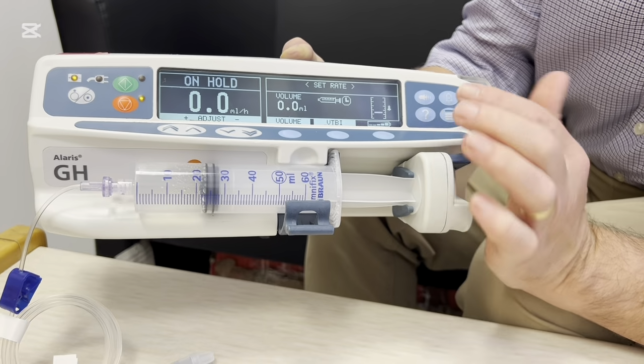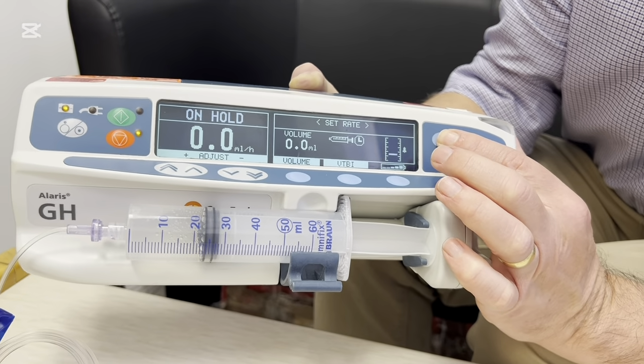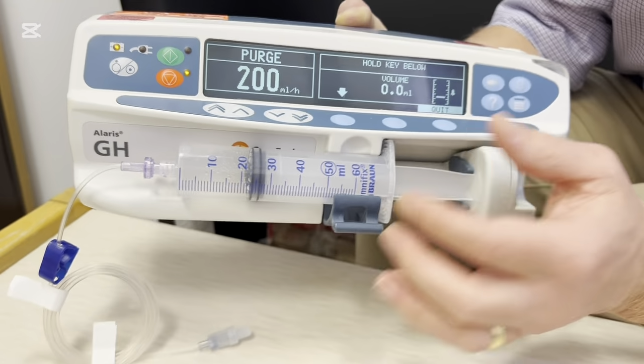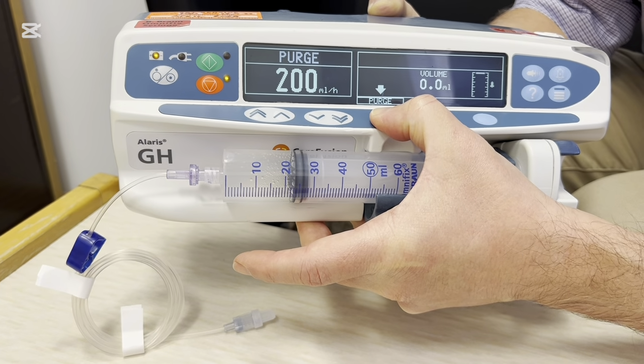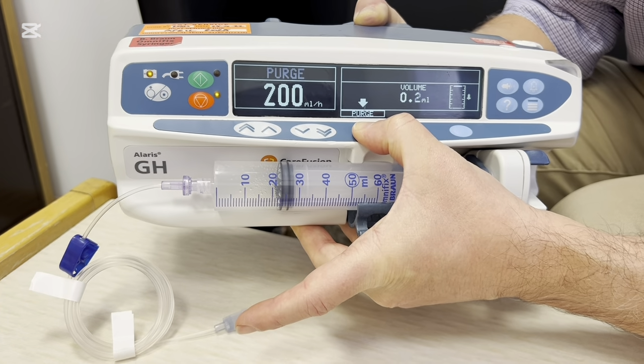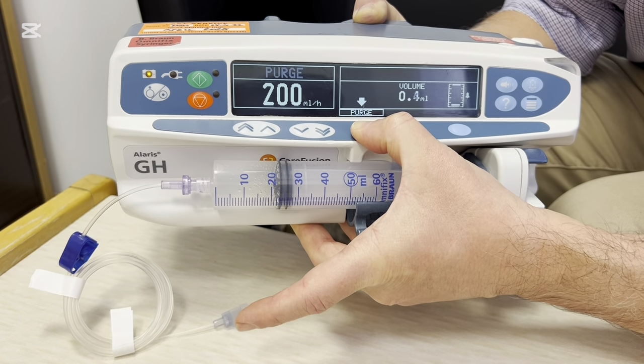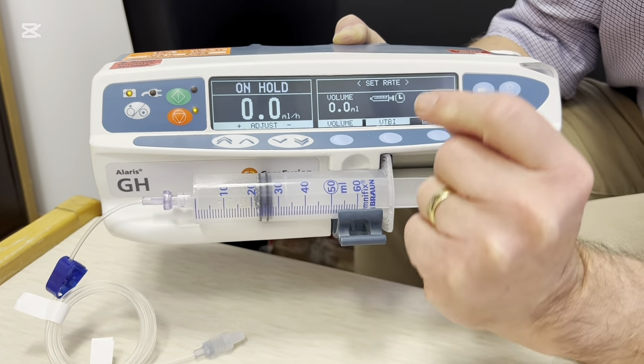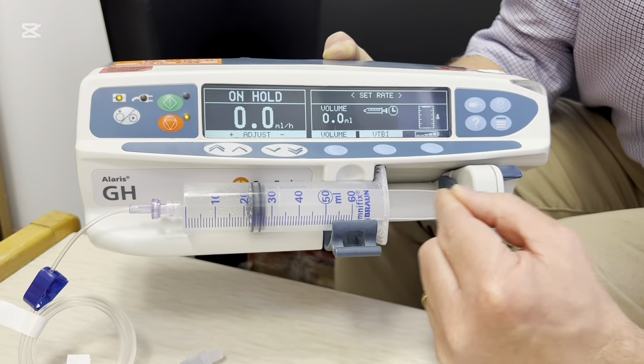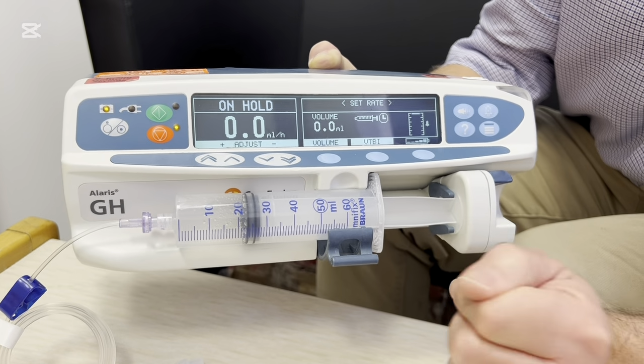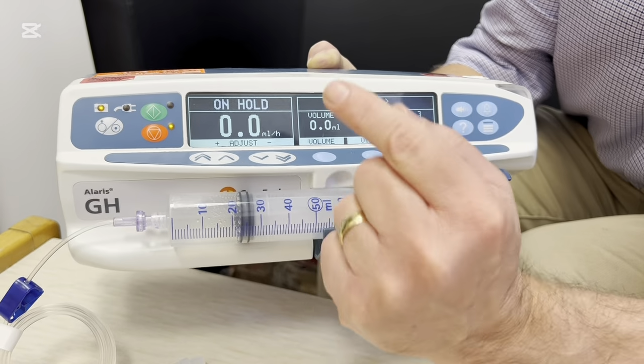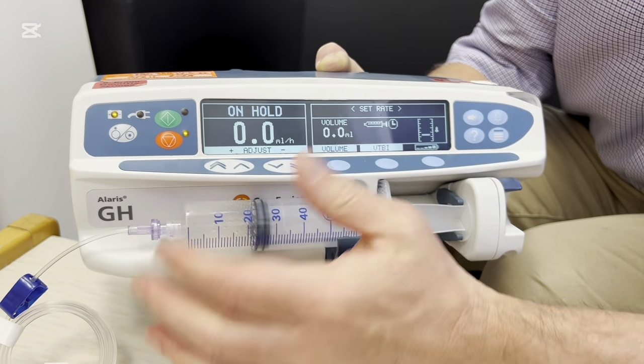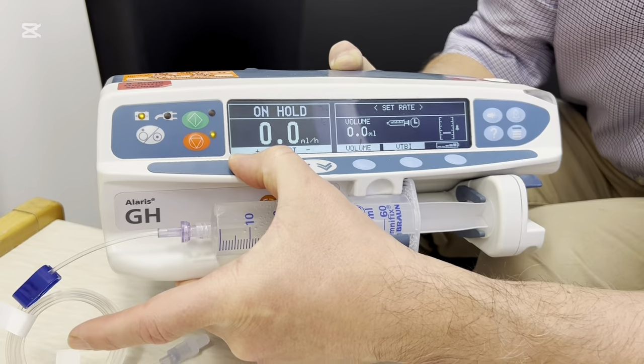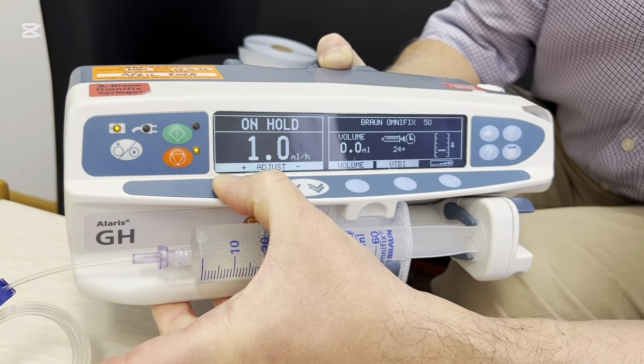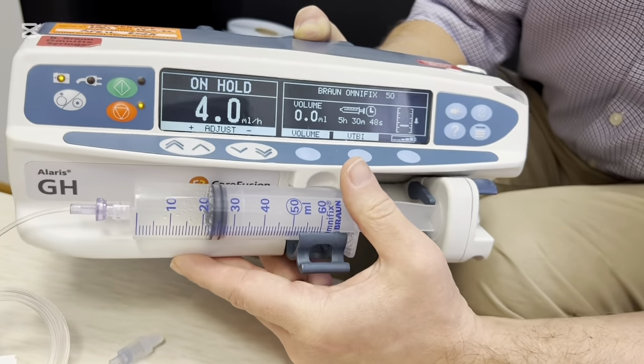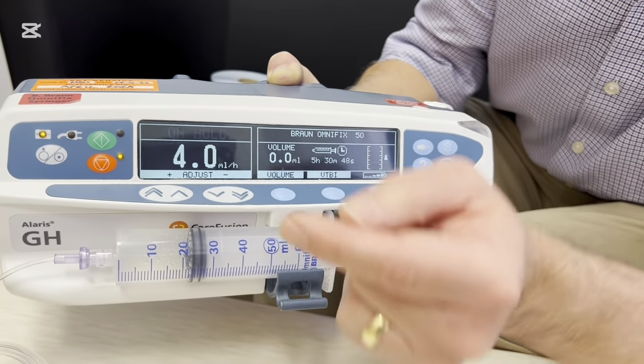Having placed the syringe into the syringe pump, you need to purge to make sure that the line is primed and that it's taking up the mechanical slack. Okay, so you can see the fluid coming out at the end of the line, so we know that the line's now purged and the device is taking up the mechanical slack, so that as soon as you press start, it will start to deliver the fluid to the patient. Having primed the line, we now want to set the infusion rate, so we press the up arrows, and that gives you coarse changes in infusion rate, and then press start.